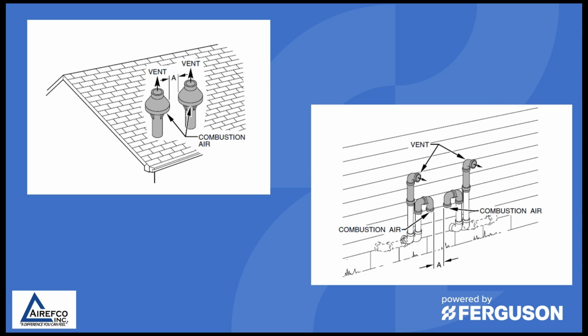When twinning gas furnaces, the venting requirements remain the same: the concentric kit that is used in most applications, and the two-pipe arrangement. One thing that you want to make sure of when you're venting twin furnaces is that you vent them together and do not send one out one side of the building and the other one out the other side or out the roof. If you do this, and the wind is blowing on one side of the structure and not on the other, you could have pressure switch trips, and this could be a real problem when you have twin furnaces.